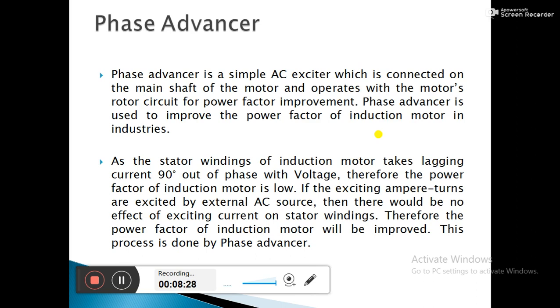The third and last method is the phase advancer. A phase advancer is a simple AC exciter connected on the main shaft of the motor, and it operates with the motor's rotor circuit for power factor improvement. It is used to improve the power factor of induction motors in industries. The stator winding of the induction motor takes lagging current 90 degrees out of phase with the voltage, resulting in a low power factor. If the exciting ampere-turns are supplied by an external AC source, there is no effect of exciting current on the stator windings, and therefore the power factor of the induction motor is improved. This process is performed by the phase advancer.